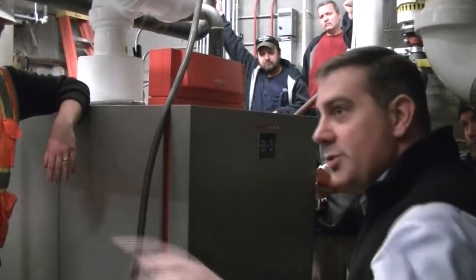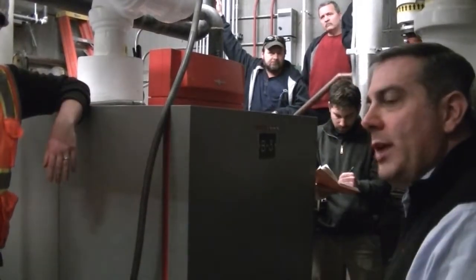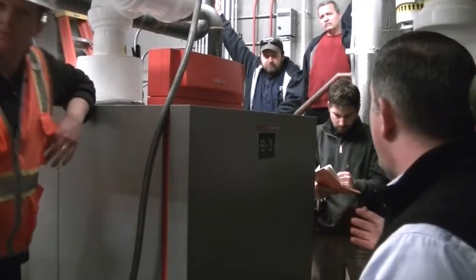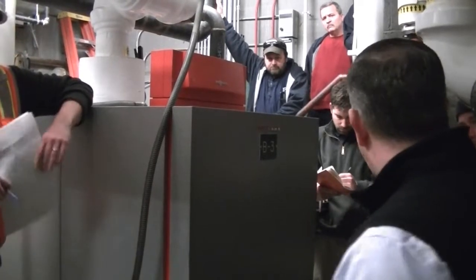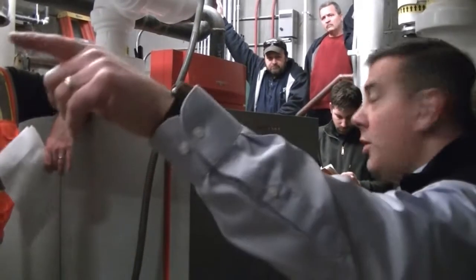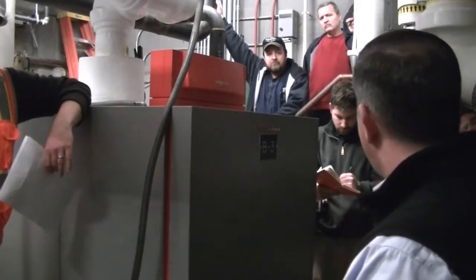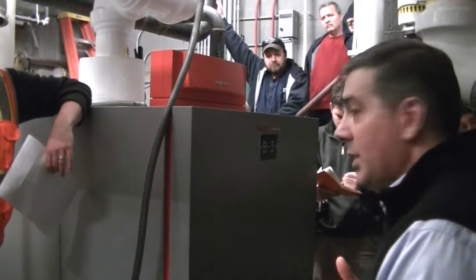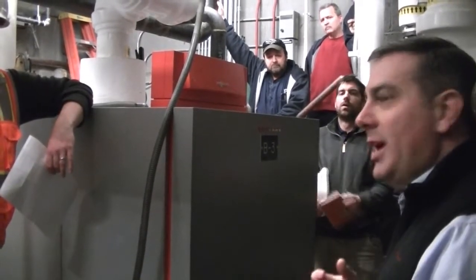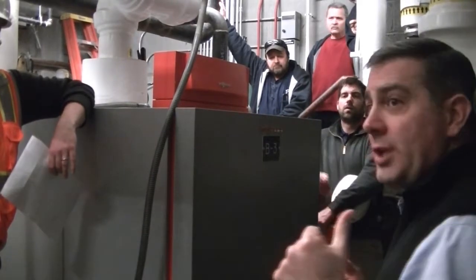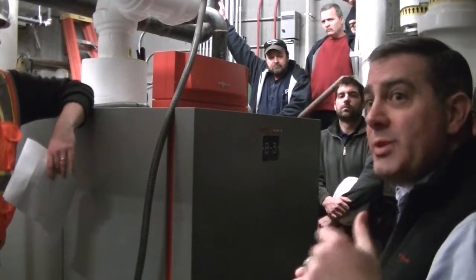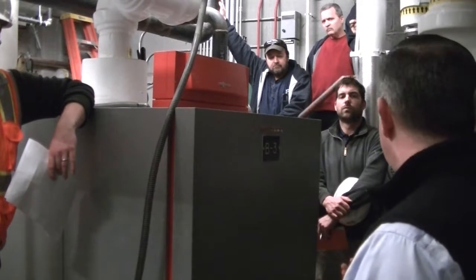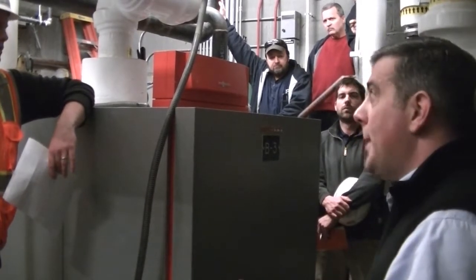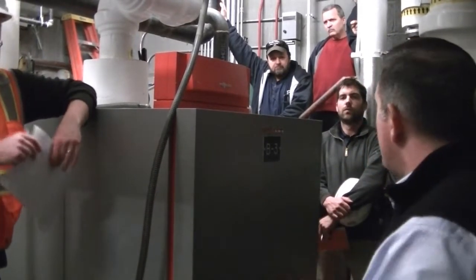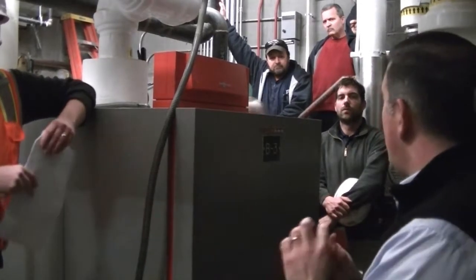And what you'll see, some of you that are in front of the boiler control down there, you'll see boilers number 1 through 5. When you look at the boilers, you're only seeing 4 Viessmann boilers. One of the boilers that are showing up on our screen is actually the cogen plant that's outside. And in this case, that cogen system has been configured as boiler number 2 in this package. What's that? Well, I'll explain. So as far as our system knows, it's boiler 2.